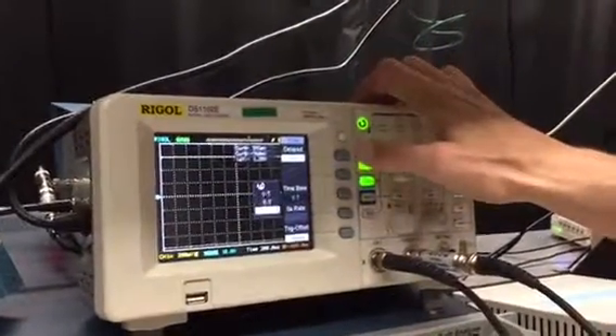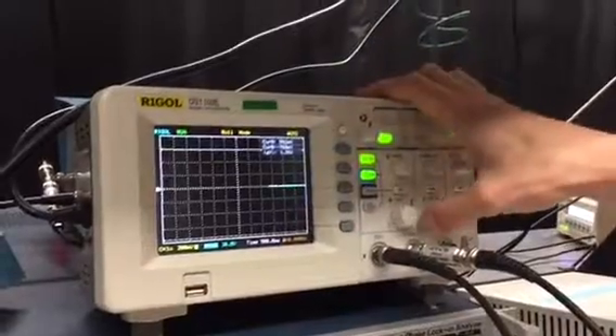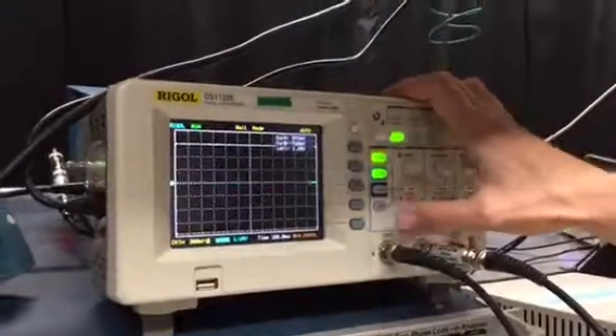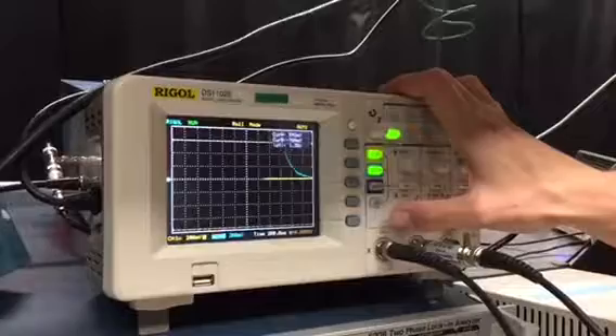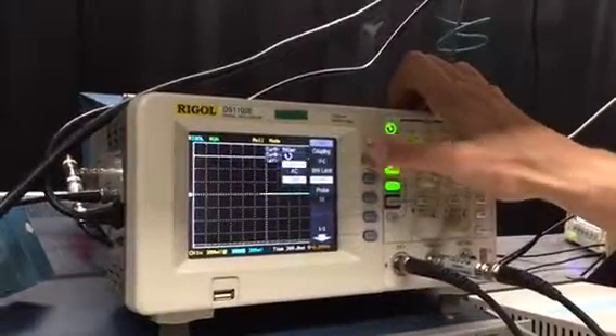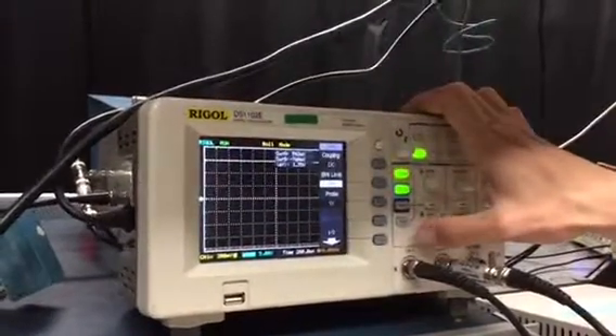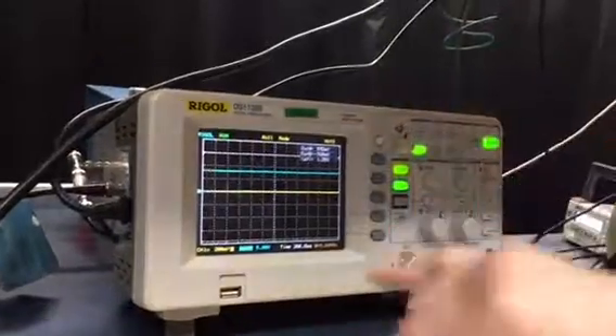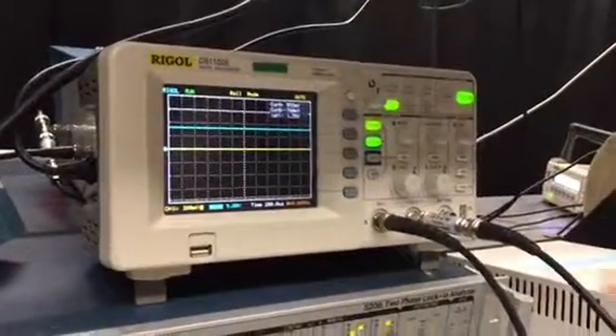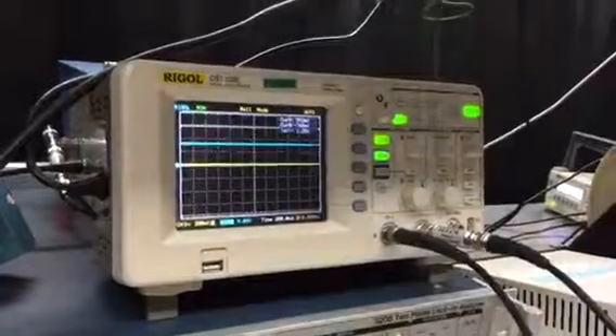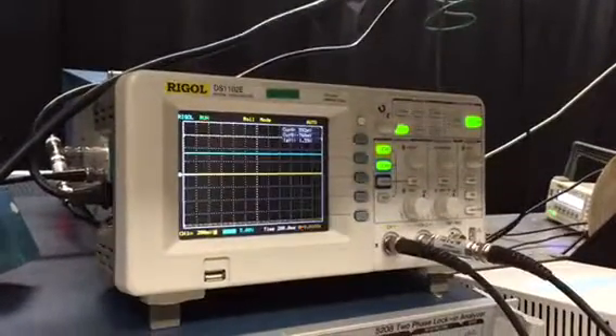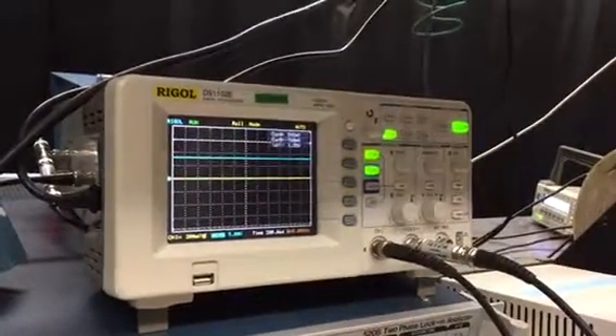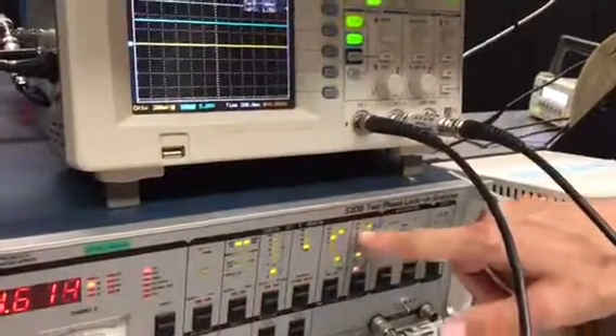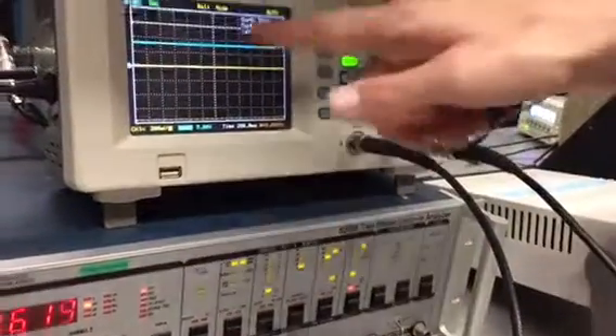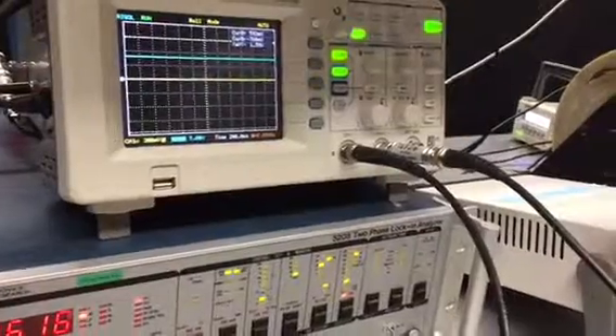So for the purpose of calibrating this, we can just set it to roll, and we'll make sure that is DC coupled. So right now, completely off resonance, that is the signal which is feeding through, and we want to get that to be much, much smaller. So remember, we want to turn the sensitivity of this up by another factor of 20 and have that close to 0.